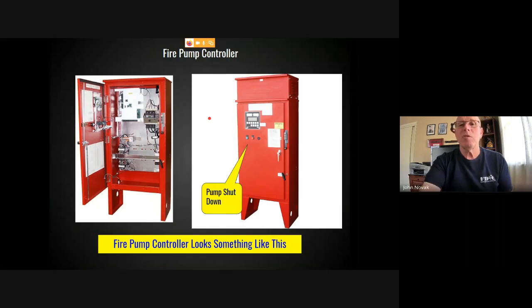Again, when you're dealing with fire pumps, if the fire pump is not adequate to support your standpipe operation and your chauffeur hooks up to the fire department connection and is pumping to the system, the fire apparatus pressure is going to be greater than the fire pump, so it's basically going to shunt the water flow from the fire pump. That means the fire pump is going to be running at churn. So in that case, it's recommended that someone go in and shut the fire pump off, and then just use the fire department apparatus to supply the system.